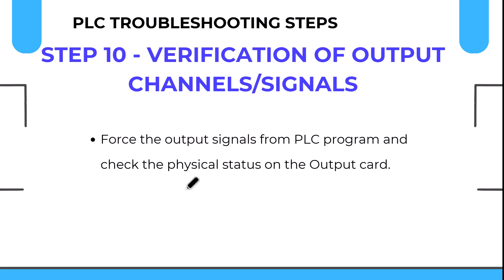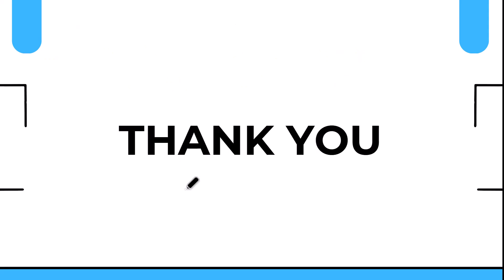To verify whether a channel is faulty or whether a signal is reaching the input card, go to the PLC program or hardware configuration and inspect that specific channel. Similarly, the status of PLC output channels can be verified by forcing a signal onto the specific channel in the PLC program. A technician can then check whether the 24V digital output signal is appearing on that specific output channel, confirming the output card is functioning correctly.